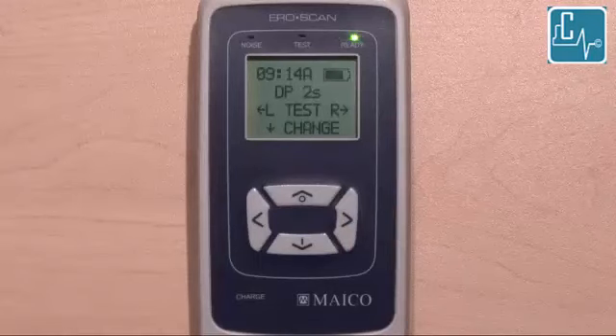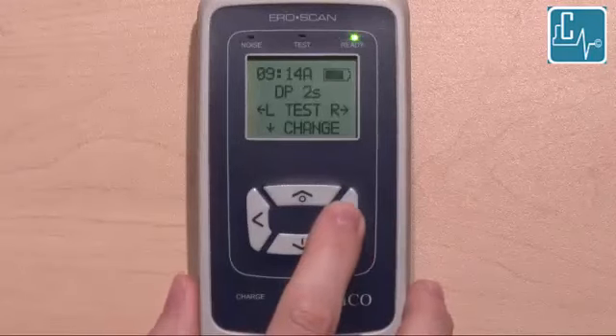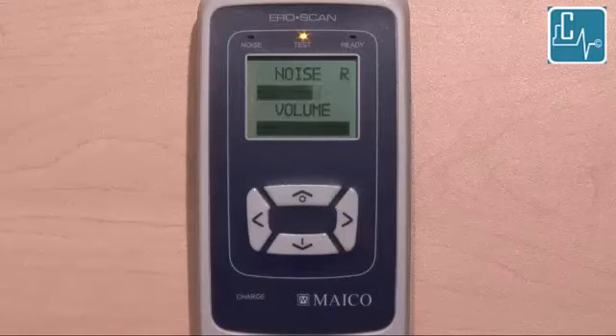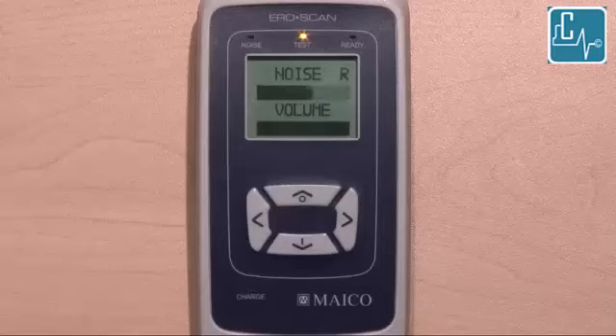select the ear to test using the appropriate arrow key. The test will begin automatically by conducting a probe check. A noise and volume bar will appear on the screen. These two indicators look at the level of the noise present and also the space or volume of the ear canal. You should see these bars decrease in size when the probe is placed in the ear.